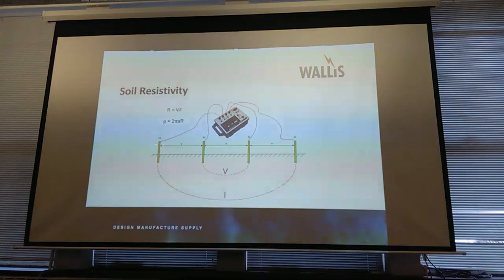So depending on how far apart your probes are, that's how far you're looking into the ground. So we will carry out a series of surveys, ranging from about half a metre apart right up to 100 metres apart, depending on your substation size. You take all those readings and you carry out one or two surveys around the site to give you as much data as you can, to make sure all the data is coming together.